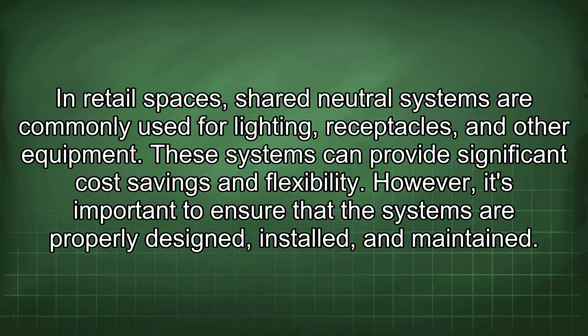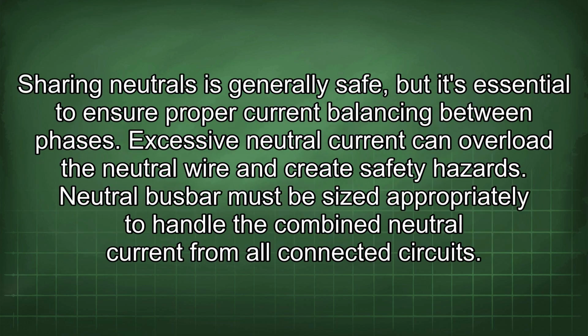In retail spaces, shared neutral systems are commonly used for lighting, receptacles, and other equipment. These systems can provide significant cost savings and flexibility. However, it's important to ensure that the systems are properly designed, installed, and maintained. Sharing neutrals is generally safe, but it's essential to ensure proper current balancing between phases. Excessive neutral current can overload the neutral wire and create safety hazards.